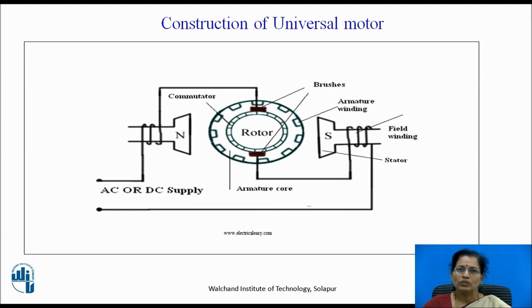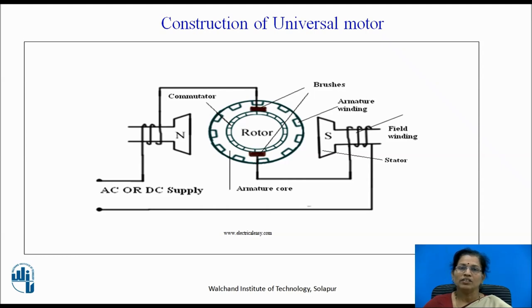Now let us discuss about the construction of universal motor. You can see in this diagram the stator, which consists of the field winding having the field poles N and S. The winding is provided to create the magnetic field in the motor. The second part is the rotor — rotor is nothing but the armature — having the laminated armature core with number of slots. In those slots, the armature winding is provided, and the commutator is given, with the winding connections connected to the commutator.